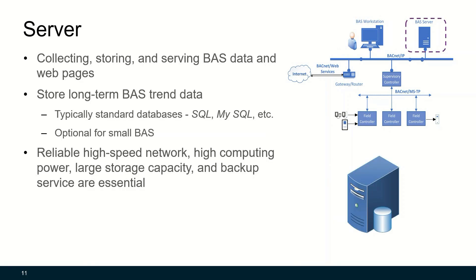A server in a building automation system is used to collect, store, and serve BAS data and web pages. It is used to store long-term BAS trend data. Typically you have a standard database like SQL or MySQL, though this is optional for small systems. For a BAS server, reliable high-speed network, high computing power, large storage capacity, and backup service are essential.